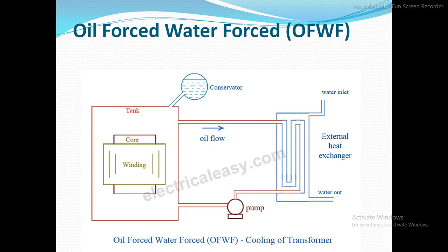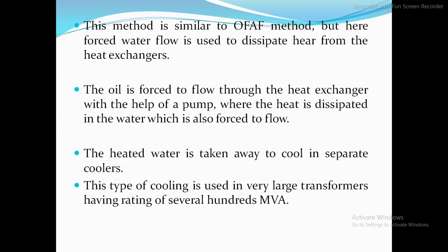The circulation of the oil is done by the pump, and the heat from that heated oil is removed by the water, cool water. So this method is similar to OFAF, that is oil force, air force, but here forced water is used to dissipate the heat from the heat exchanger. The oil is forced to flow through the heat exchanger with the help of the pump, where the heat is dissipated in the water which is forced to flow.